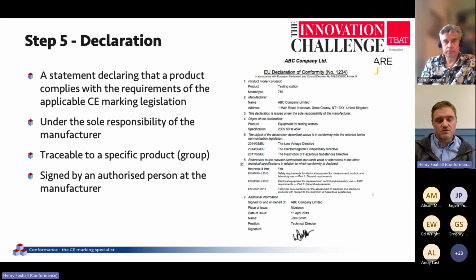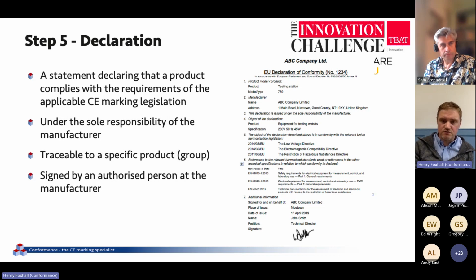And the final step, as we've talked about before, is to have a declaration of conformity. And this is a statement declaring that a product complies with the requirements of the applicable CE marking legislation, and it's under your sole responsibility as a manufacturer. The distributor, the importer, doesn't sign it, the manufacturer does. But remember, you become the manufacturer if you rebrand anything that's been made elsewhere.